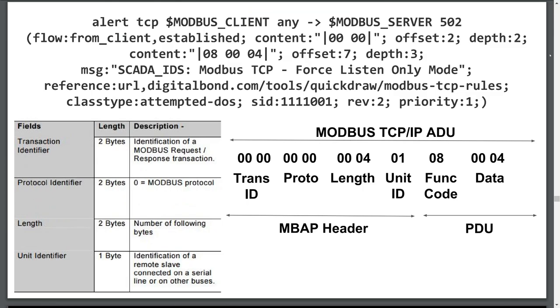It then compares the next three bytes, which is the Modbus PDU, containing the function code and data fields. It then matches it with a diagnostic function code of 8, and a subcode for force-listen-only mode. If the signature matches, it logs the packet, sends an alert, and displays what's in the message field.